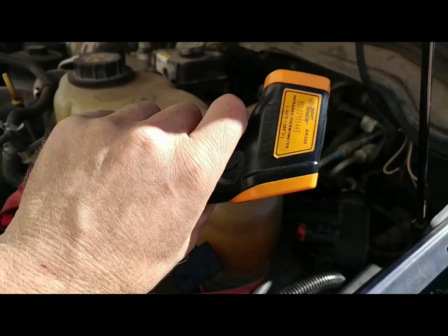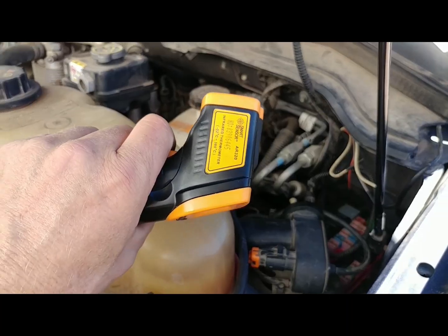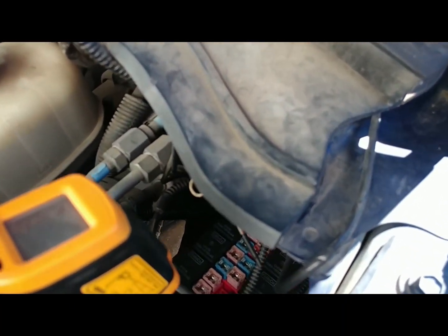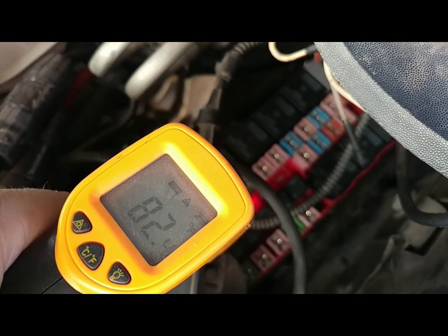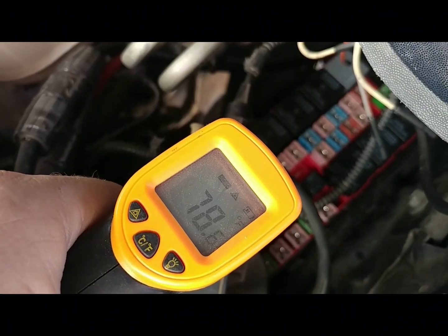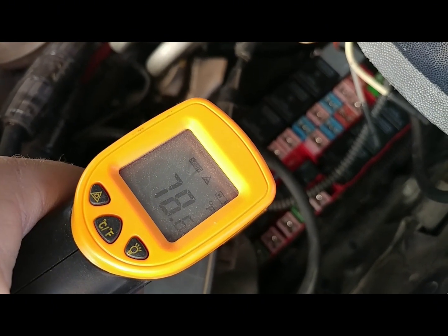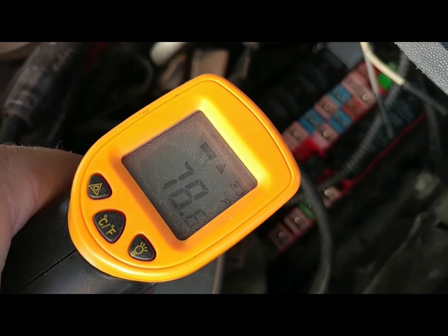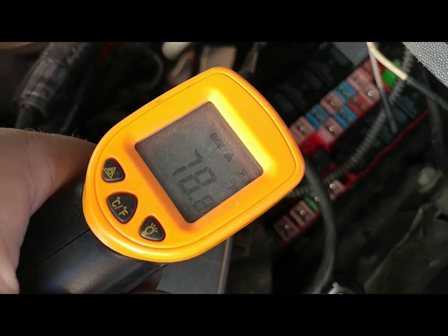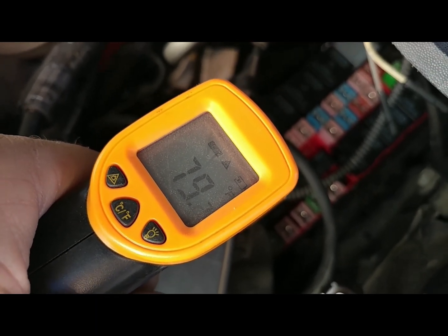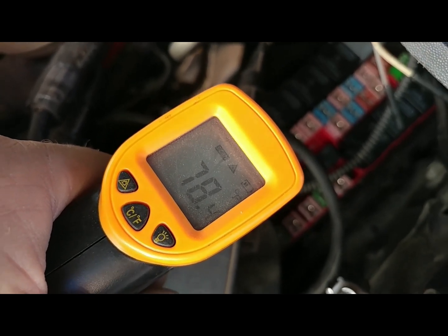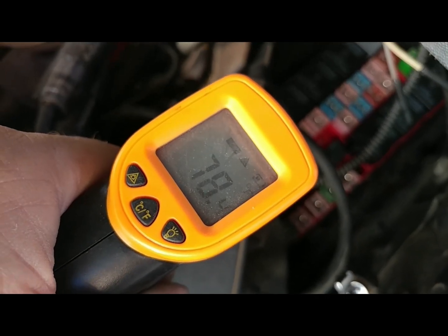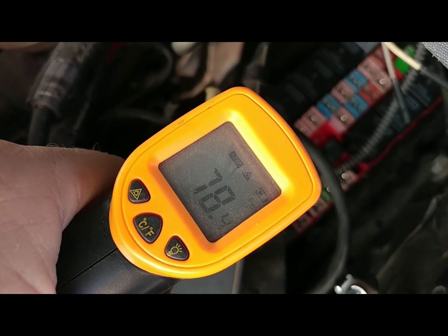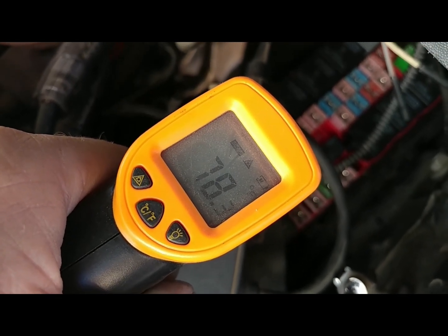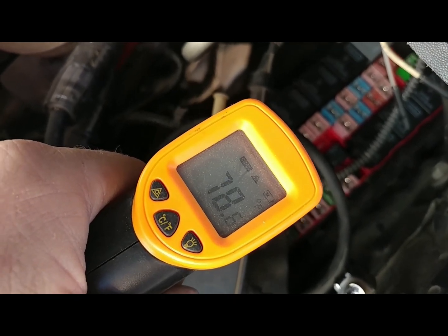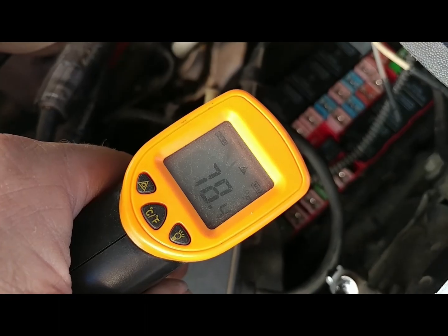One thing I might suggest is to check your fuse with a pyrometer, and you can see I'm right on top of it. We're at 78 degrees. If the fuse were sitting in the slot and not fully engaged, it'd be arcing, which would bring the temperature up over 100. I always question a fuse that's anything over about 105 degrees. So if you're getting excessive temperatures on your fuses, you've got another problem, like high resistance in a wire, or burnt laminations from a motor that's drawing excessive current.